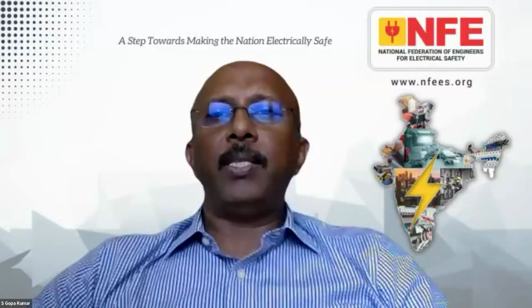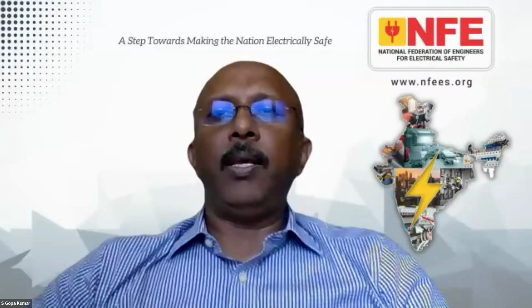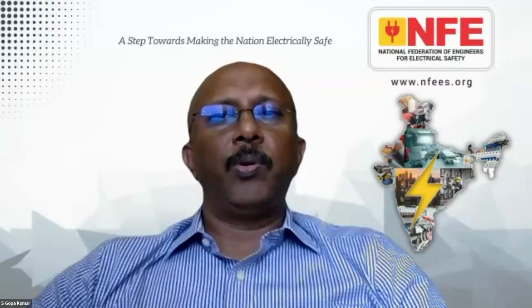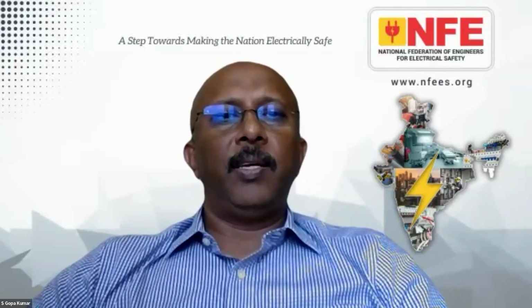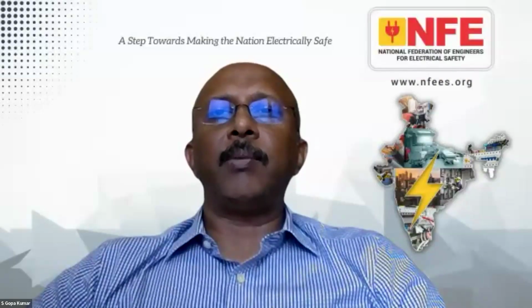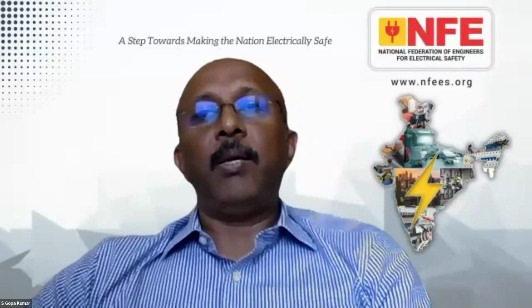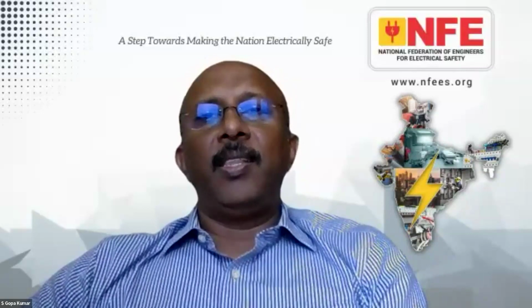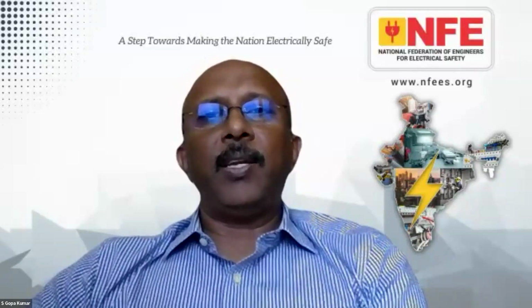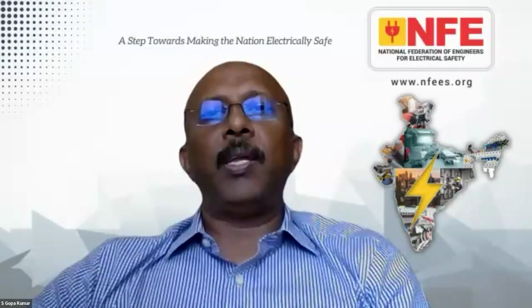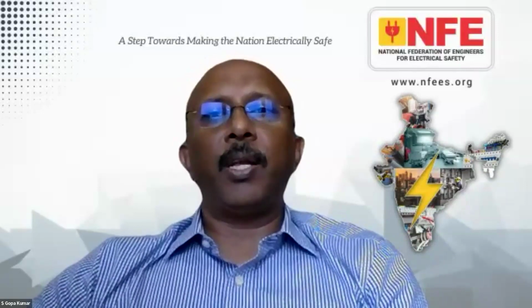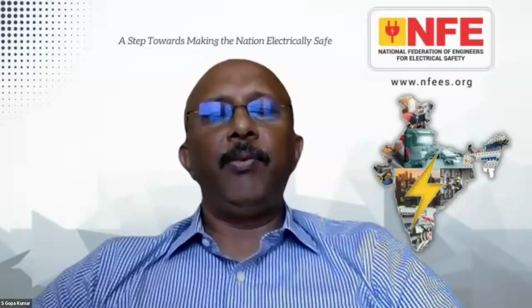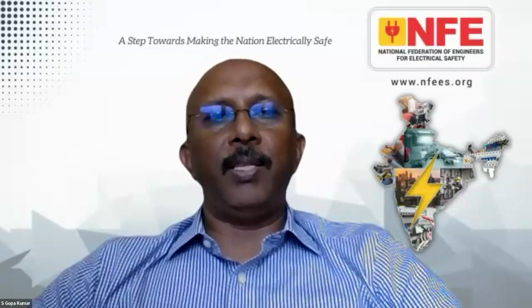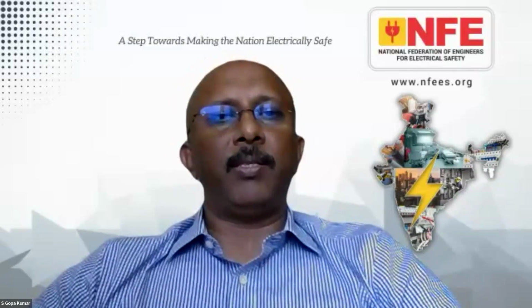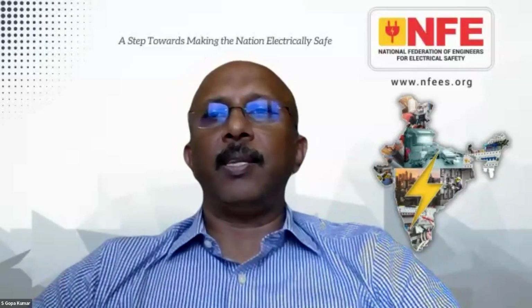The next question from Mr. Keshavam: is fault loop impedance applicable for IT earthing system also? Mr. Girish, any answer? Of course, it is not applicable in IT earthing, because the concept of the IT earthing system is totally different. But very important, for the biomedical equipment or the equipment connected to the IT system, you must ensure that there is enough fault current to disconnect in case of a line to neutral fault. So the test is necessary, but earth fault loop may not be necessary.